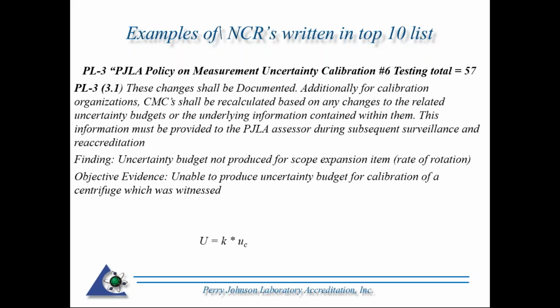Additionally, for all calibration organizations, CMCs shall be recalculated based on any changes to related uncertainty budgets or underlying information contained within. This information shall be provided to the PJLA assessor during subsequent surveillance and reaccreditation. So with PL3, we require calibration organizations to submit uncertainty budgets. And at the bottom there, those of you that are in calibration should be familiar with that formula.